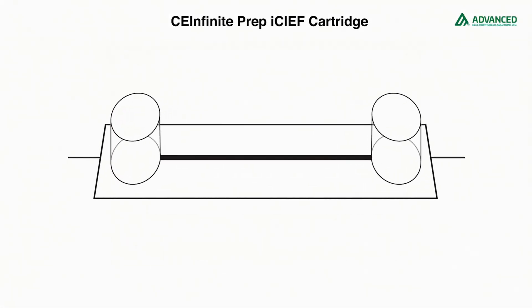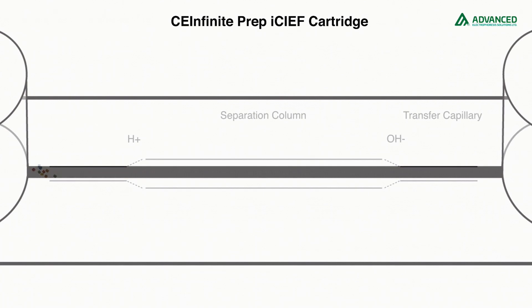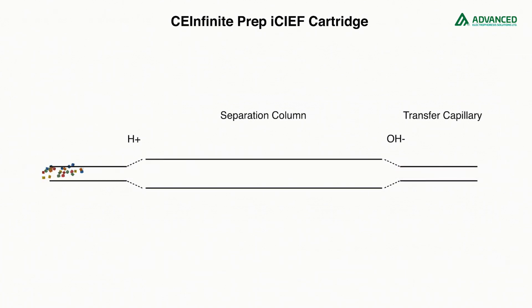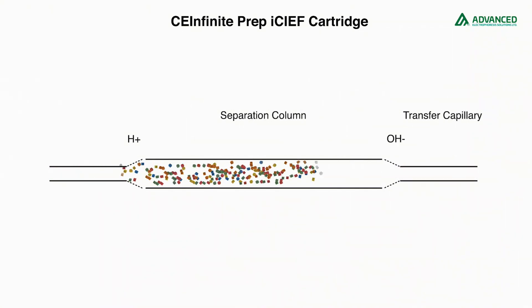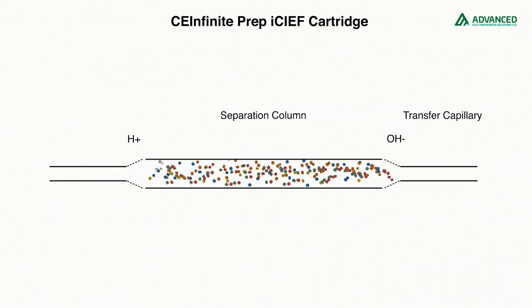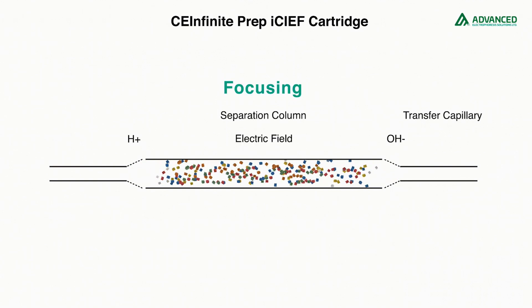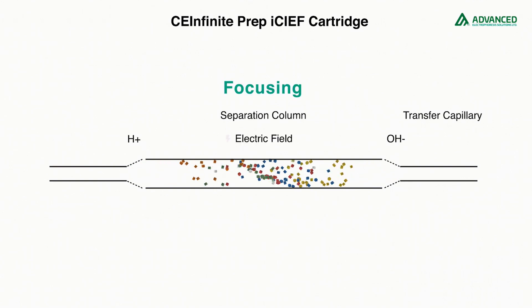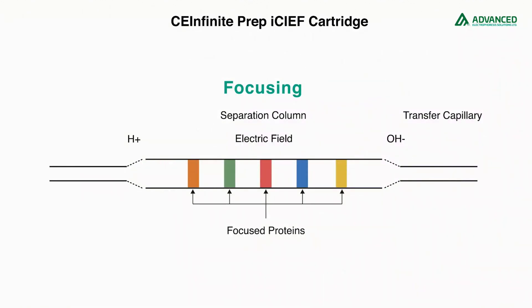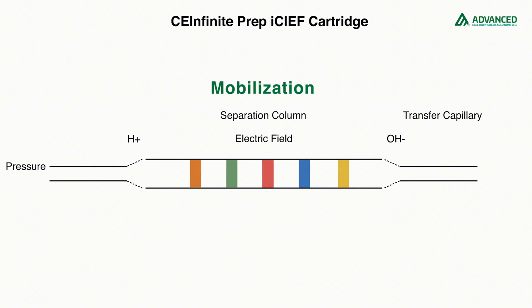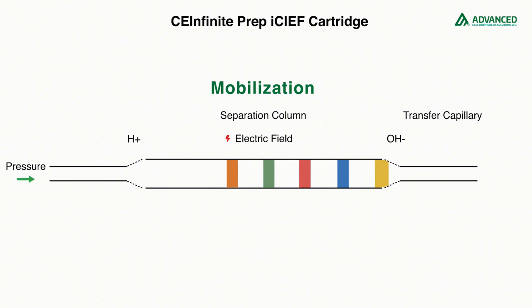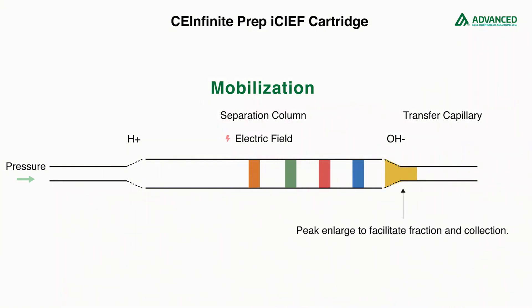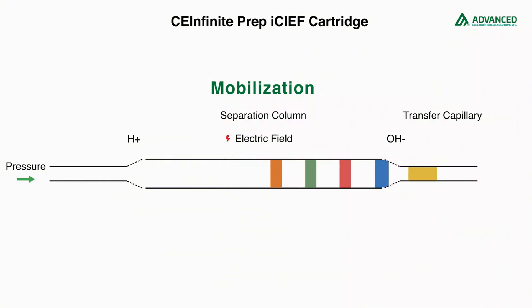AES's patented capillary diameter transfer technology and pressure mobilization strategy ensures reproducible separation and identification of protein charge isomers. Focused proteins travel from the larger diameter separation capillary to a smaller transfer capillary. This change in shape widens the focused bands allowing a longer time for collection and detection by MS.